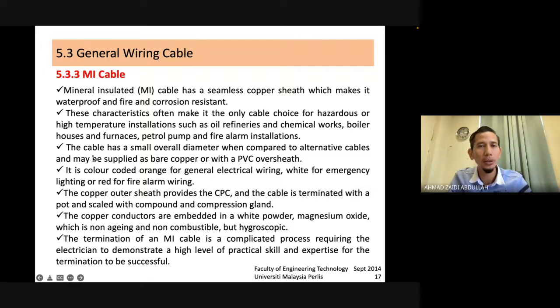The cable has a small overall diameter compared to the PVC cable. Normally the cable color is orange. At Unimap, you can go to the genset room and find a cable with orange color. That one is the MI cable, mineral insulated. The genset is a very hot environment, high ampere and temperature, so that is why we require MI cable. The copper outer sheath provides the CPC.